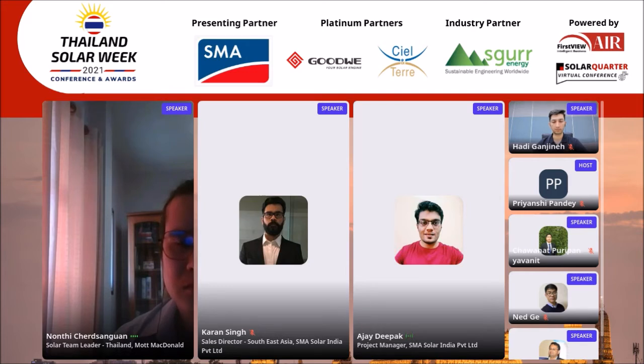That will reduce the number of MPPTs used in PV plants, and we will focus more on energy, not on power. When I say energy, it means that when we install a 50 megawatt plant, previously we may have been doing 60 megawatt DC or 75 megawatt DC maximum, but in future it's going to be like 100 megawatt DC, almost double the DC capacity ratio. Why do we do that?